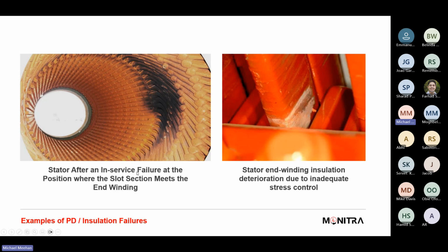So this is a stator after in-service failure at the position where the slot sections meet the end winding. So you can see end winding again is always, well, not always, but it's a very high risk area in the way that the machine is constructed. There's some good and bad machine designs, and there's some very good ones out there, which mean that end winding discharges are not really an issue based on well manufactured and well built machines. And then there's other machines which maybe are not so well built, and you end up with these type issues.